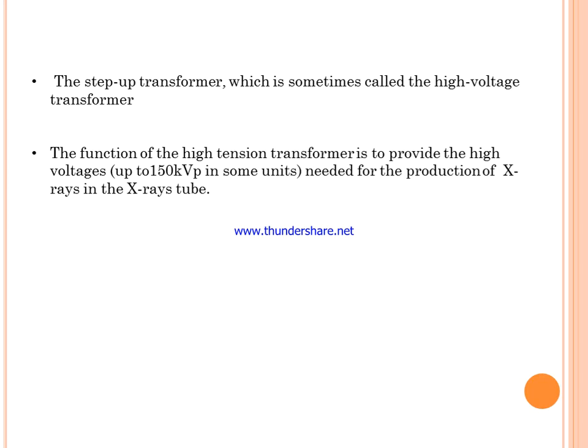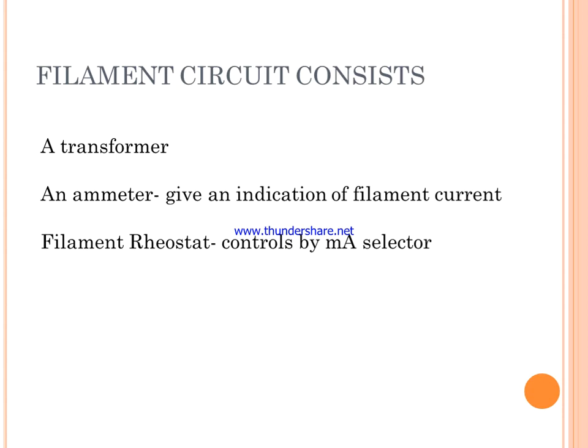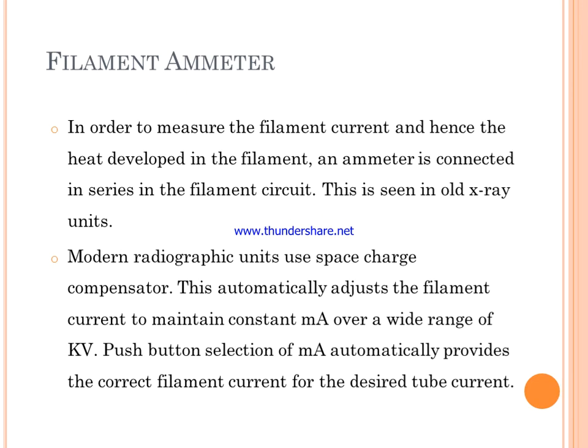The step-up transformer is sometimes called the high voltage transformer. Its function is to provide the high voltage needed for the production of X-rays in the X-ray tube. The filament circuit consists of a transformer and an ammeter which gives an indication of filament current, and a filament rheostat which is controlled by the mA selector.